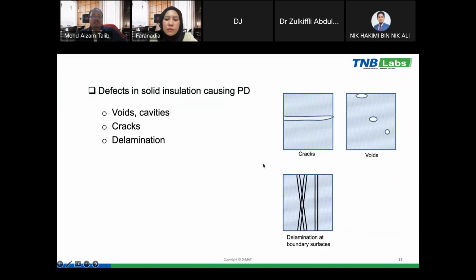For solid insulation, a factor that causes partial discharge is a crack. Also, sometimes when the manufacturing process is not good, it will cause the presence of voids during manufacturing, and also delamination at the boundary surface. For example, in the power transformer, we laminate the conductor with paper insulation, and delamination of this kraft paper at the boundary surface will create partial discharge.